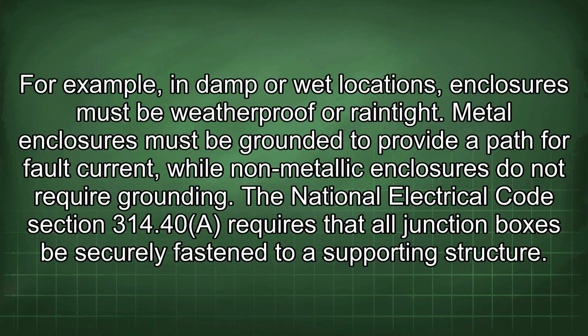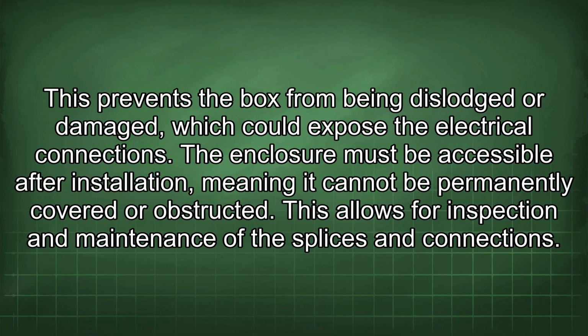Metal enclosures must be grounded to provide a path for fault current, while non-metallic enclosures do not require grounding. The National Electrical Code Section 314.40 requires that all junction boxes be securely fastened to a supporting structure. This prevents the box from being dislodged or damaged, which could expose the electrical connections. The enclosure must be accessible after installation, meaning it cannot be permanently covered or obstructed. This allows for inspection and maintenance of the splices and connections.